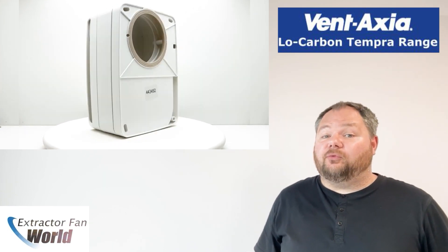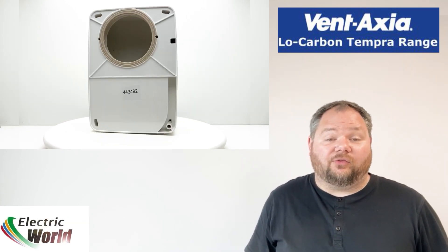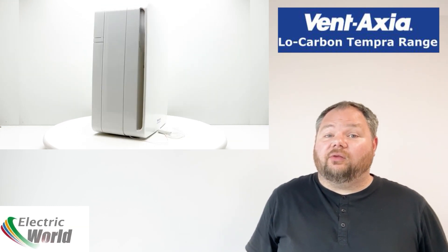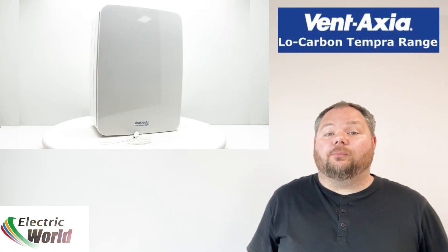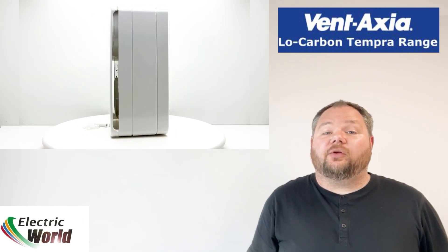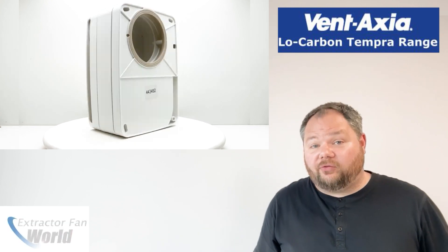The unit also meets the building regulations performance requirements for continuous extract ventilation. The Tempra is also designed so that the replacement air being introduced is at a reduced rate, ensuring that the room being ventilated is still under a slight negative pressure. This ensures that fresh air is brought into the room from the rest of the house, preventing humid air migrating.